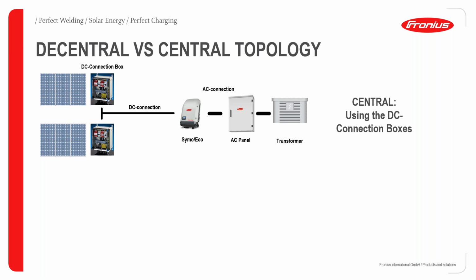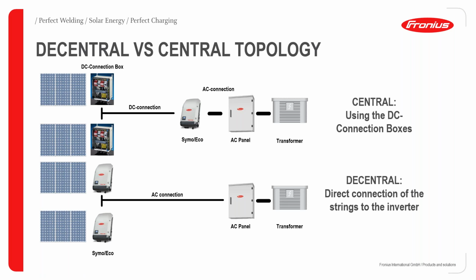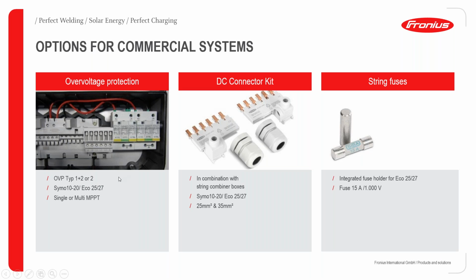So let's now talk a bit about the topology for commercial systems. It can either come pre-combined or direct. For centralized connections, you can have all the connections done using a DC combiner box and then come with larger diameter cables and connect to the AC panel for onwards transformation. But you can also have it decentralized, that is connected directly to the inverters, and then travel with the AC connection to your AC panel and of course to the transformer. Options for commercial systems exist because we also have DC overvoltage protection. We have a DC connector kit, which helps you to connect larger diameter cables.